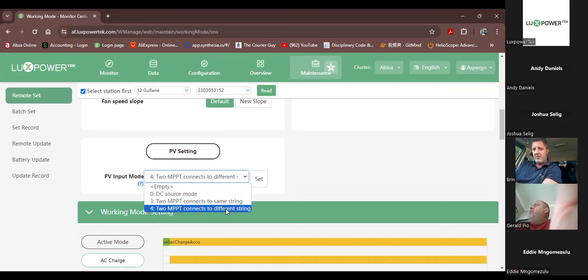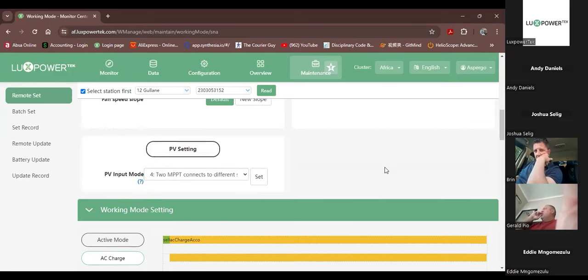Or this one is the common one, where you're bringing down sets of strings and you run it through your protection on the PV input board, and then they go in independently into the machine, okay?